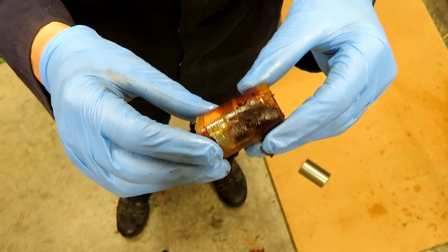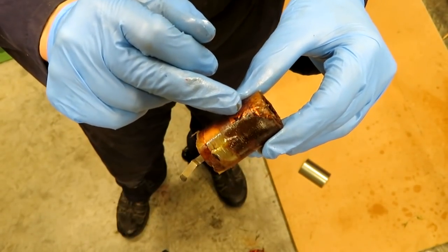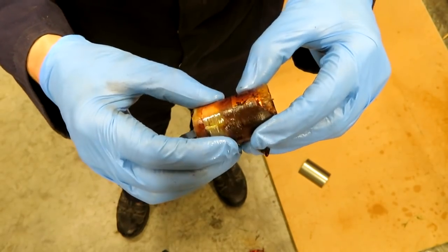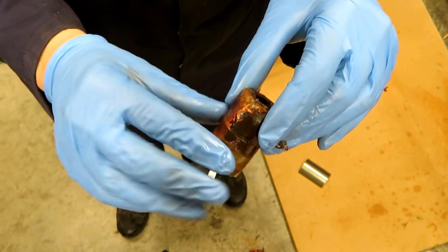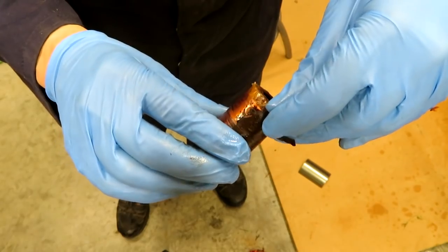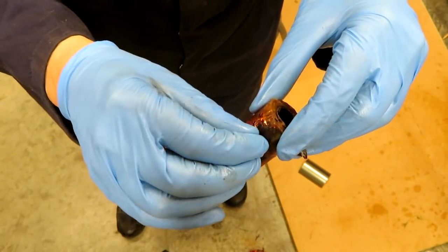So looking at this secondary winding, I can clearly see now this burnt patch. So that's why our transformer actually failed. The windings have shorted together and burnt, because this is covered in layers of paper.